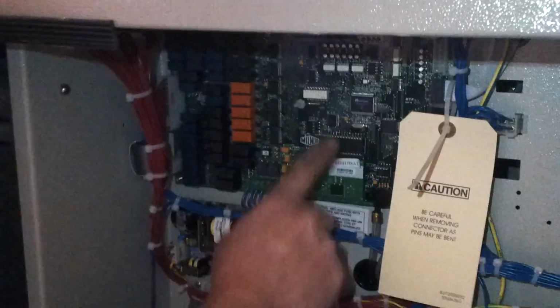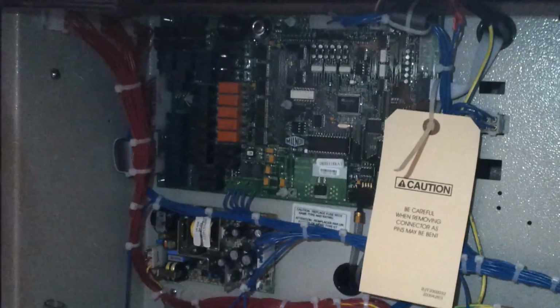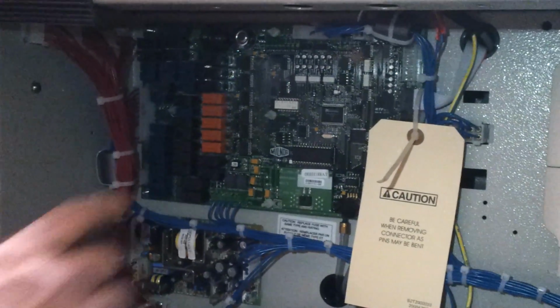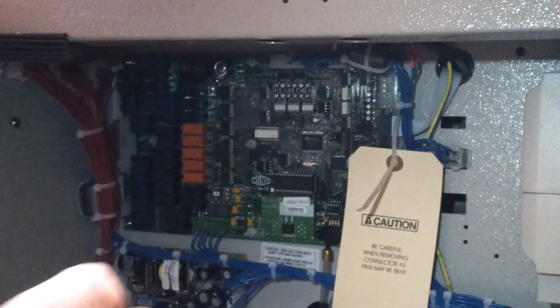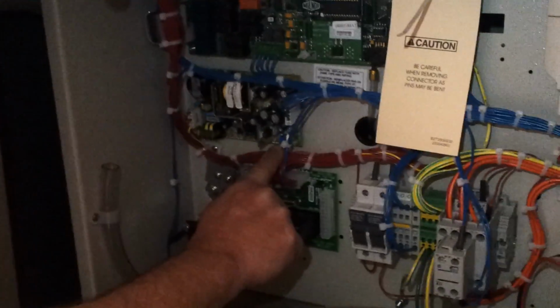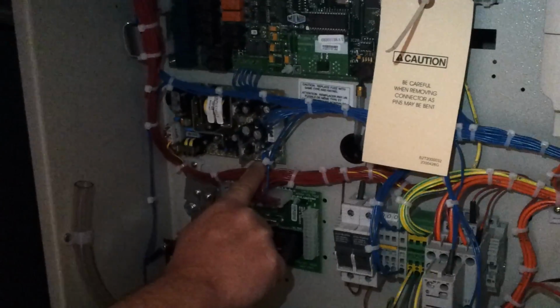So if say you lose your display, you have no display but your fuses are all good, and you check your voltage here and your voltage is lower than 5.01, what you can do is there's a little blue potentiometer that's right here, and it has a little baby screw on it. If you turn that screw to the right, it increases the voltage to the processor board. If you turn it to the left, it decreases voltage to the processor board. So if for some reason you were to lose your display, this would be where you'd want to start looking to make sure that you have your proper DC voltage going to your processor board.